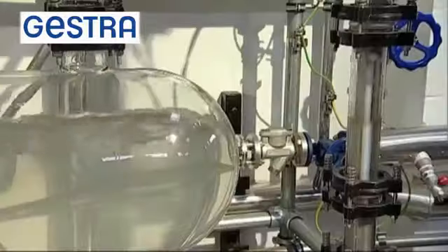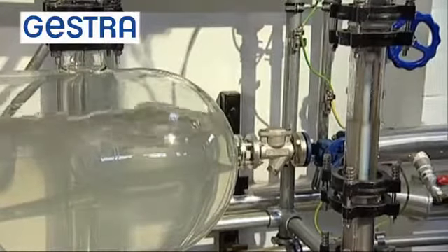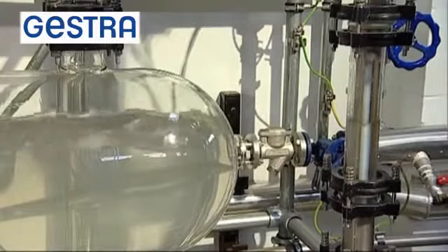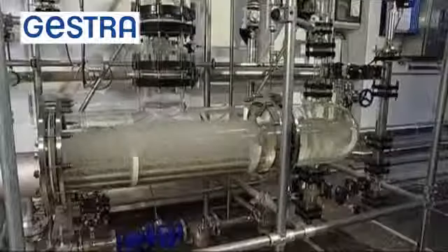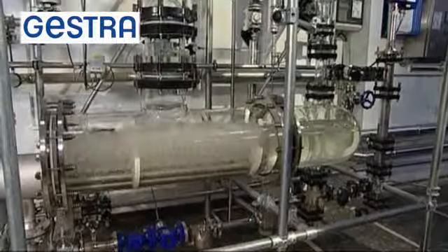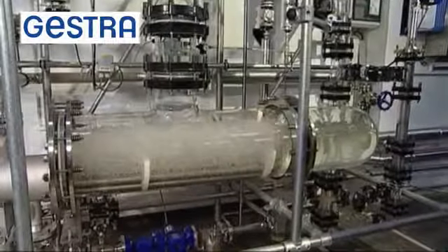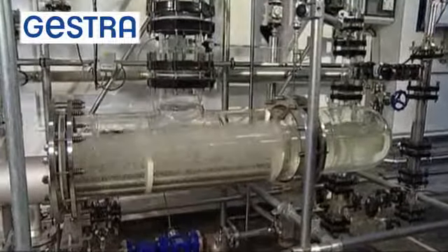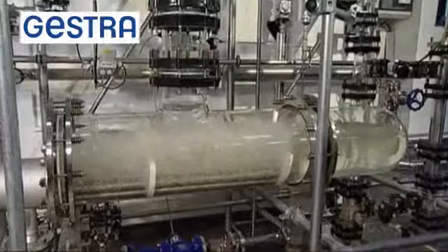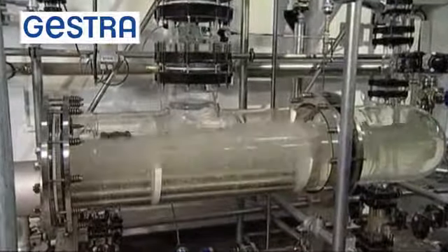When the steam outlet is closed again, the water level drops, since the quantity of steam bubbles in the water space quickly decreases again. In such a case, it's possible that the water level may drop below a preset limit, which will shut down the firing equipment. Here it's necessary to use a 3-component control system to consider the steam outlet, the feed water supply, and the water level in the steam boiler, and therefore prevent premature throttling of the feed water control valve.